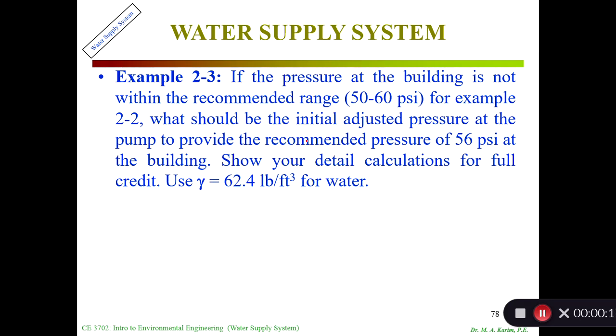In the second problem, Example 2-3, we say if the pressure at the building is not within the recommended range of 50 to 60 psi, for example in problem 2-2 we already got 43 psi, what should be the initial adjusted pressure at the pump to provide the recommended pressure of 56 psi?